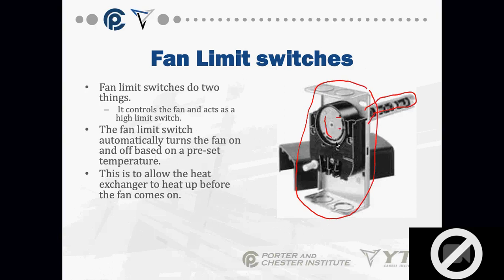This dial has three settings on it, and I'm going to talk more about those three settings. It hits a set of contacts mounted in this plastic, and it opens and closes switches based on the mechanical motion in this dial. These are slowly going away. If I had to guess, in 15 years you will not find these fan limit switches on any piece of equipment that's being sold. But right now these are still extremely in use. We're going to more digital controls, but right now you are going to see these on the majority of oil forced air equipment.